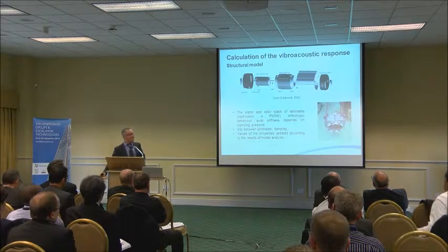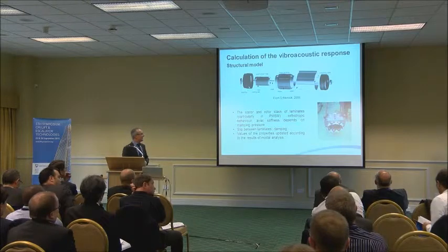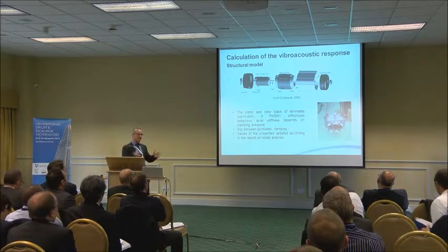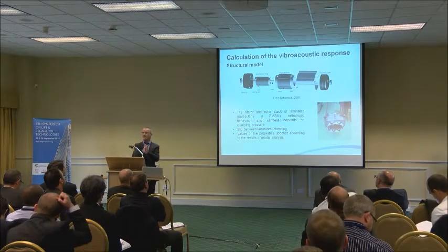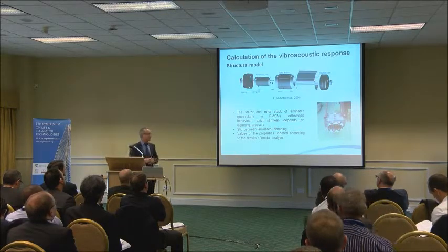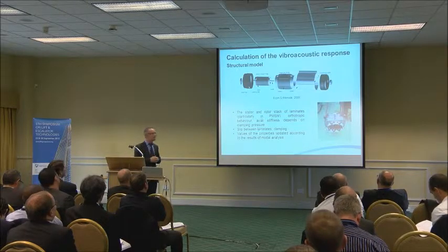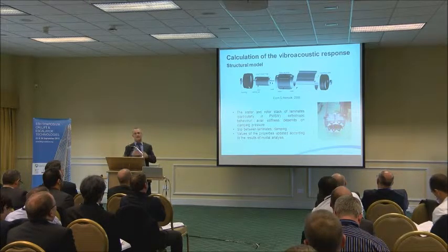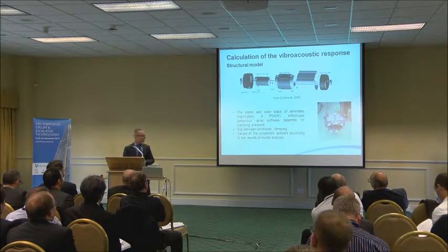Regarding the structural model, there are several components, and we developed the model. Concerning the stator, it is composed of a pack of laminates, and this is why some of the properties have a different performance in different directions of space. So it has an orthotropic performance. For instance, stiffness is much lower in the axial direction than in the radial one.